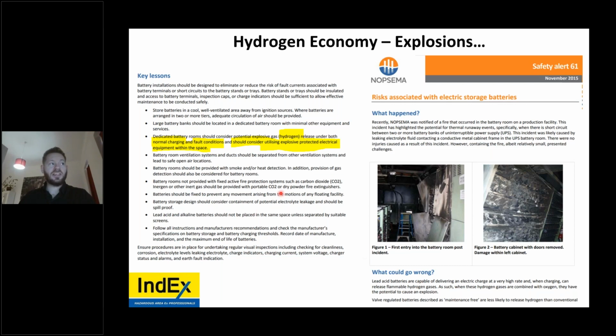Now, the key lessons that NOPSEMA calls for is dedicated battery rooms should consider potential explosive gases, hydrogen, released under both normal operation, and here's the key one, fault conditions. Most people do not consider fault conditions. Nothing will go wrong. As someone with many years of experience, and all of these articles found easily in the last 30 minutes, that is incorrect. They happen constantly. Faults happen constantly. So you should consider use of explosive protective, so hazardous area equipment.